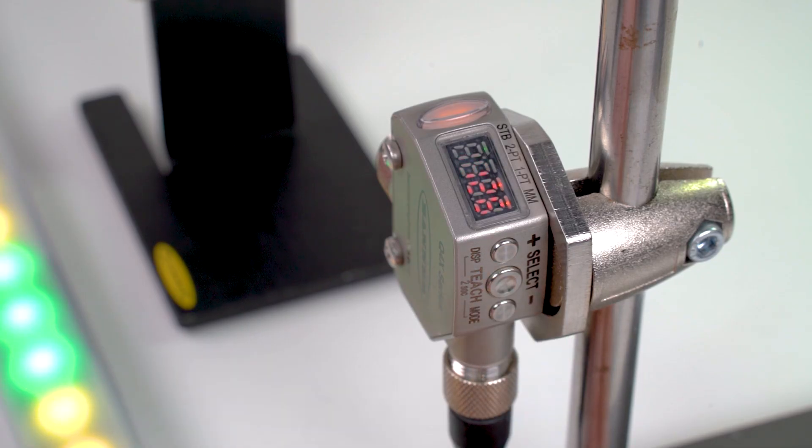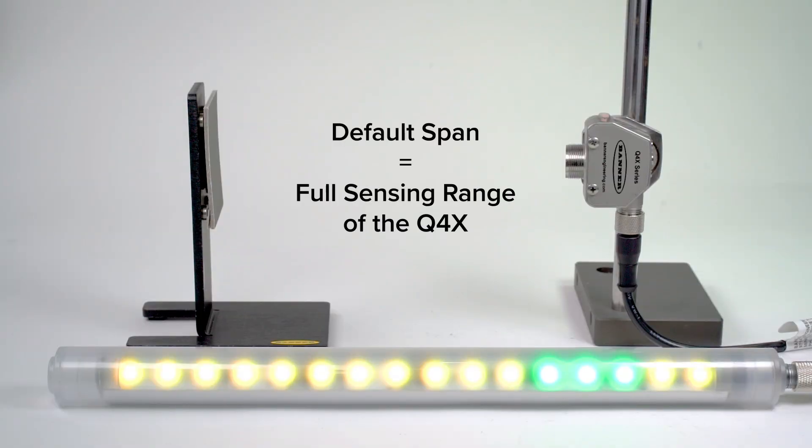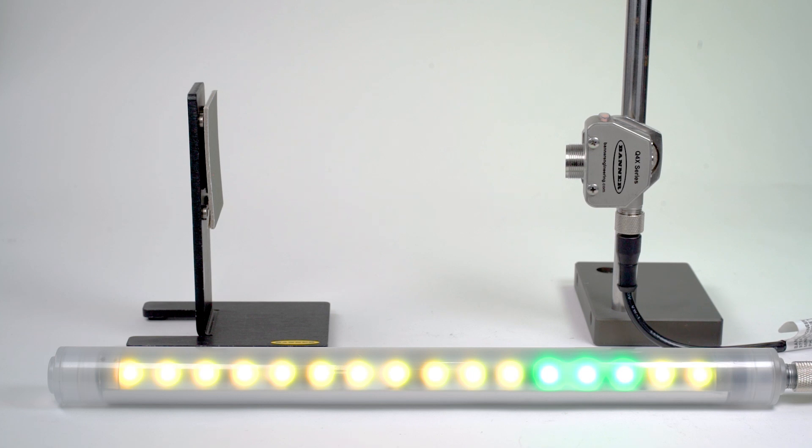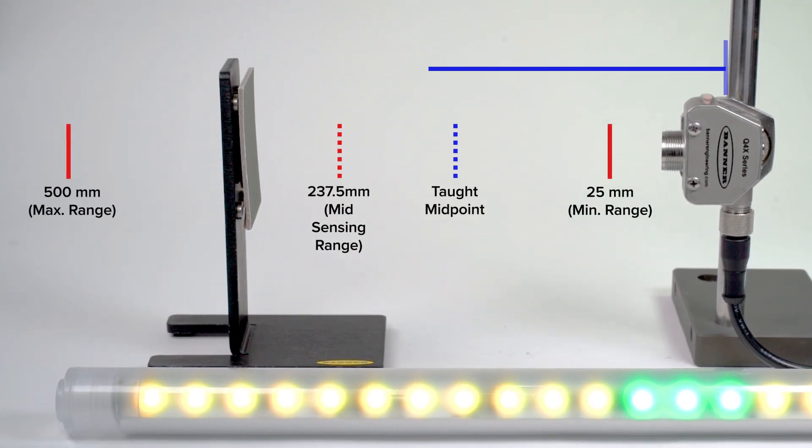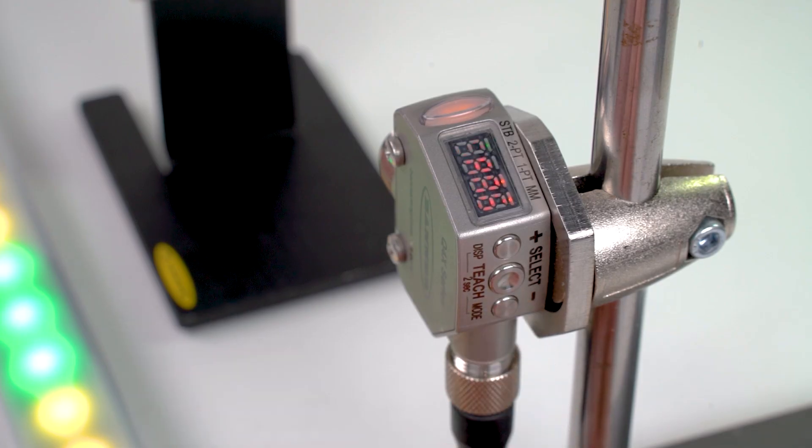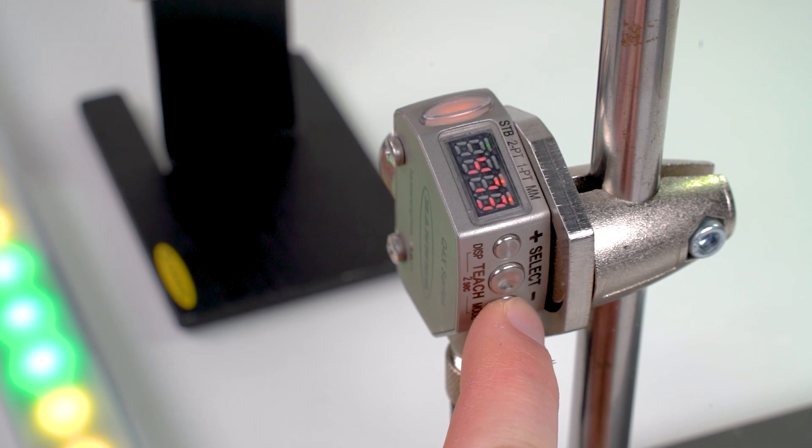The default span of the measurement range is equal to the full range of the sensor, so you will likely have to adjust it manually after teaching the sensor to ensure that you are making use of the full analog signal. For example, a 500 millimeter model will have a default span of 475 millimeters. To dial in the span, begin by pressing the minus button and then use the plus and minus buttons to adjust the span as necessary.